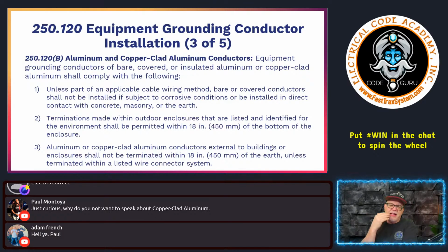And I can tell you that at the end of the day, it is still very rare to see terminations for equipment grounding conductors of aluminum or that other type of material in the larger sizes, although it could happen more often than with smaller branch circuits. Even though the code doesn't prohibit somebody from making a 12 gauge or a 10 gauge aluminum circuit conductor, there's nothing in the code that says you can't. It's just most manufacturers are not going to do it because we're going to use copper for that. But at the end of the day, if you did have it and you terminated it, it can't be within 18 inches of the earth.